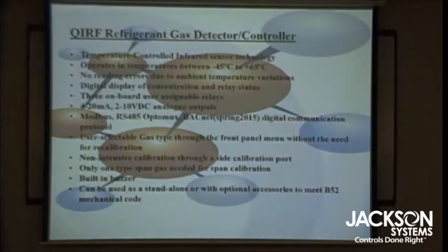The old types, the way people used to do it before, is they would have one monitor, and then they would use a sample draw system through using solenoid valves to monitor points maybe 600 or 700 feet away. The problem with that is if you had 8 or 9 points, it could take you an hour before you read point number 1 again. It just took a long time. But by having this in situ, you don't have any problems with that.